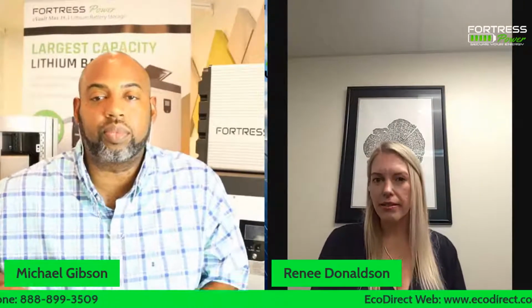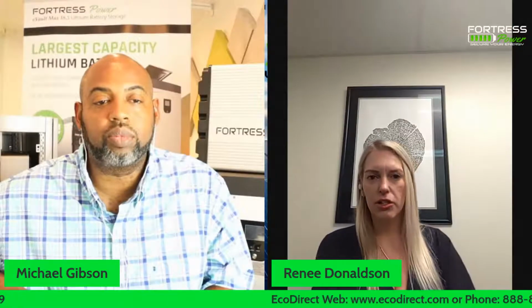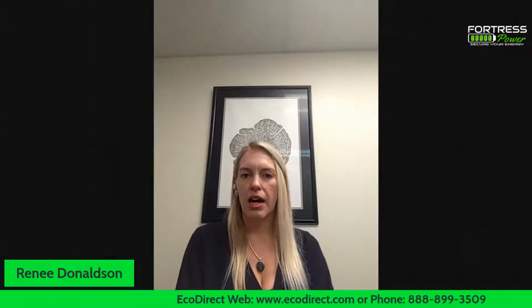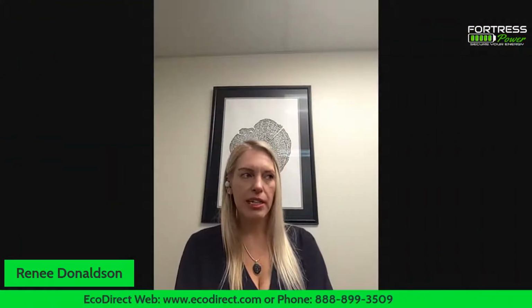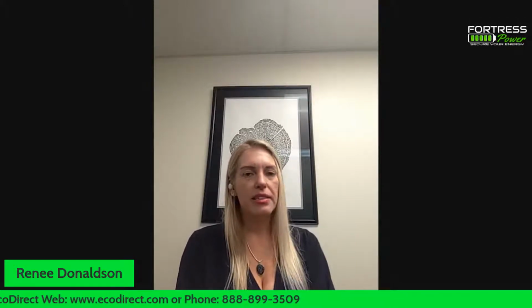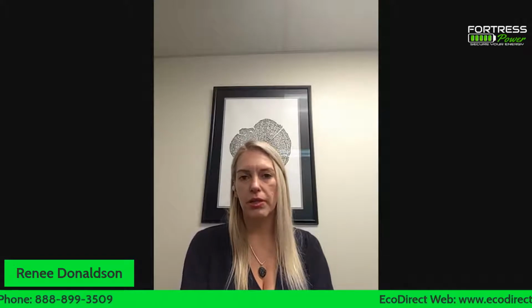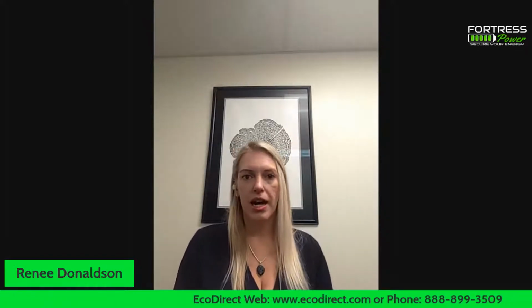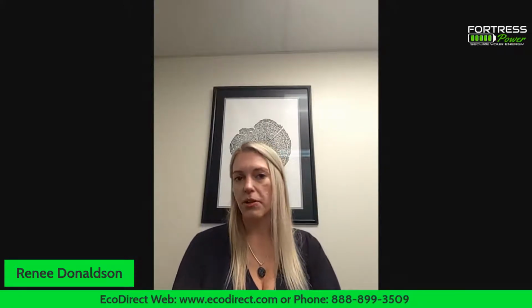You can do an existing DC coupled system—again, that's the charge controller aspect, or even potentially replacing your inverter. It really depends. If your inverter is new and your goal is to continue to have a net metered system, offsetting your consumption—if you have excess power you push it back to the grid, and at night you pull from the utility—keeping that system as is just makes more sense, both financially and from a design standpoint.